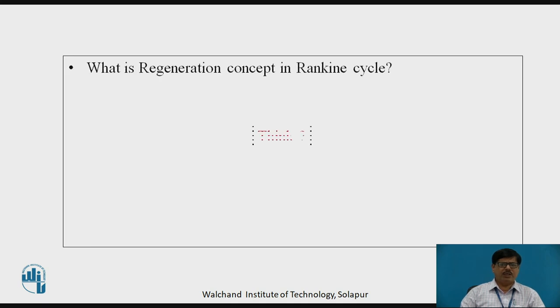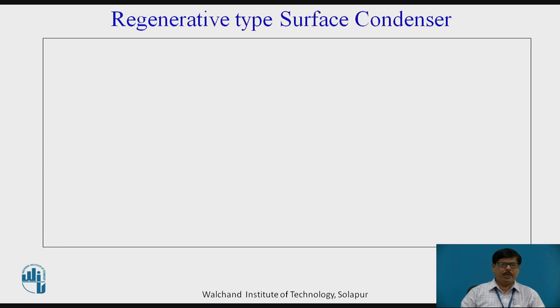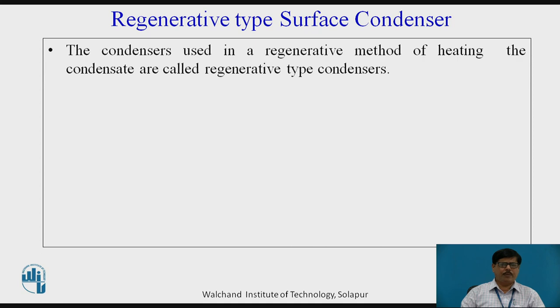Now, what is the regeneration concept in Rankine cycle? In the Rankine cycle, to improve efficiency, the steam when expanding in the steam turbine is bled at a certain point and this steam is mixed with the condensate coming out of the condenser into a number of feedwater heaters. The feedwater heaters used can be 2, 3, 4 or more, where the condensate is heated with the help of bled steam, and this regenerative concept is utilized for increasing the efficiency of the Rankine cycle. Depending upon that, another type of surface condenser is called the regenerative type of surface condenser. The condensers used in the regenerative method of heating are called regenerative type surface condensers.